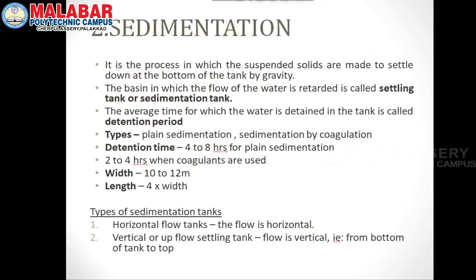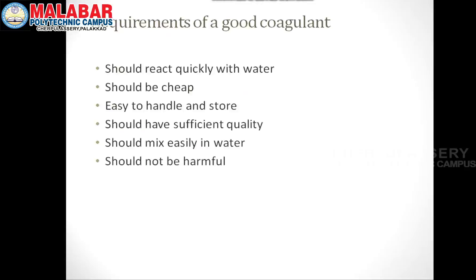This is the sedimentation process. We call the particles suspended solids. We use a sedimentation tank with a detention period. Plain sedimentation takes 4 to 8 hours, while sedimentation by coagulation takes 2 to 4 hours.